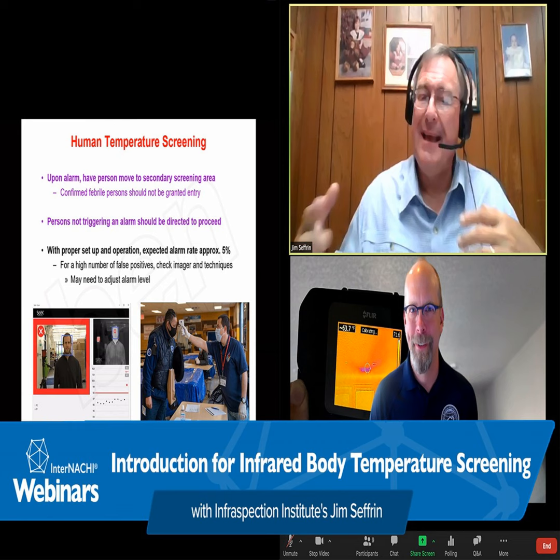Now, the current COVID-19 pandemic has resulted in unprecedented interest in thermal imaging as a potential screening tool for detecting febrile persons. However, it's again not a point-and-shoot technology. Best practices are required to ensure accuracy. The benefit to infrared body temperature screening is it provides a rapid means for temperature checks. It also allows this to be done at a safe distance where you're not at arm's length from another person. One of the components in the Opening Up America Again document that was published back in April by the U.S. government, part of the employer guidelines, states that temperature checks should be performed for employees. So it's one of 6 of the bullet points that are covered specifically.